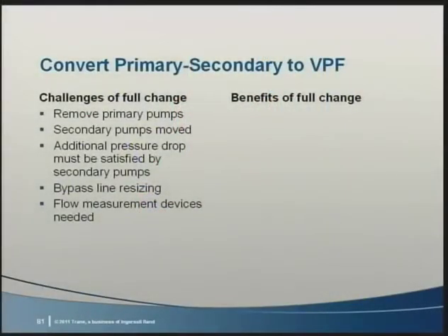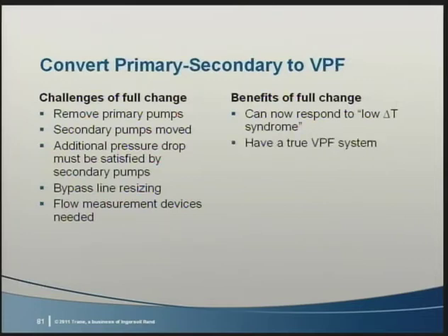It could allow the system to respond to low delta T syndrome. It doesn't fix the low delta T, that needs to be done at the air handlers, but the chillers can be overpumped and given more than their design flow without exceeding their maximum flow. This allows them to load more fully. If the entire plant is being changed, you will end up with a true variable primary flow system, and it frees up a lot of space in the room.